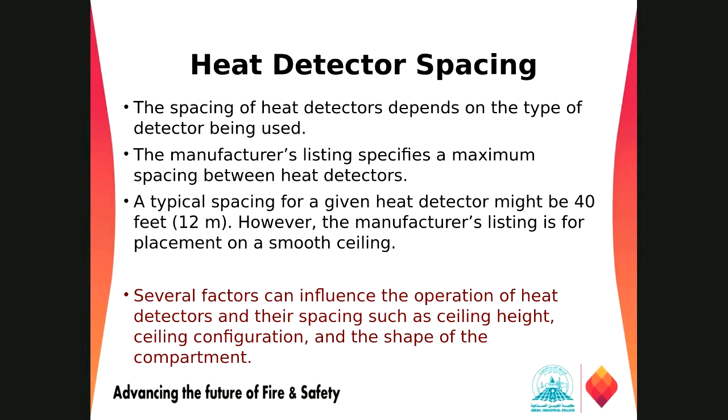But there are several factors that influence this. Mr. Rafi, yes, 12 meters between two heat detectors. Most cases, 12 meters is the maximum limit, right? But the listing is based on a smooth ceiling, with no obstruction and all. If we have obstructions, we have to change that and go back to the manufacturer requirement, right? Yes, exactly.